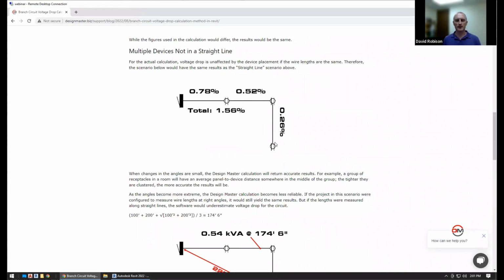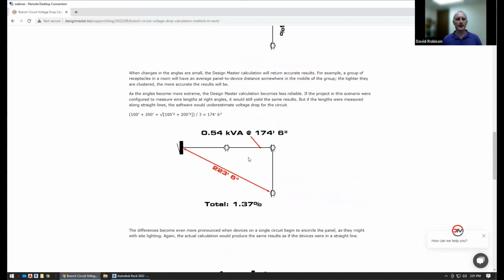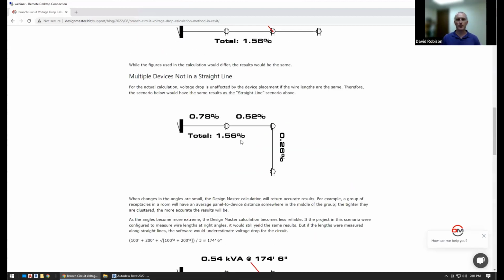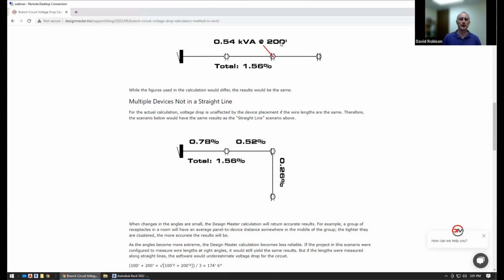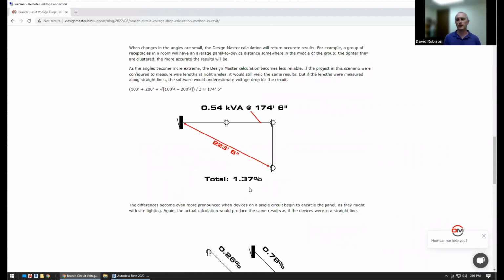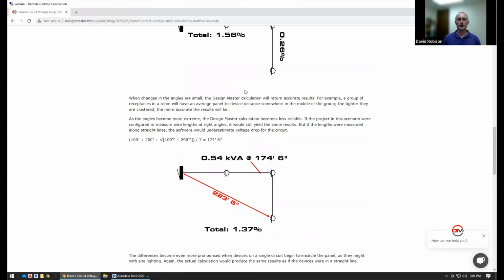So rather than having a straight line, we actually make a curve. We make a turn. So here, if you calculate it by hand, you get obviously the same voltage drop because while we've changed this location, the distances haven't changed at all. So we get the same calculated value. In Design Master, we have 100 feet and 200 feet to these two. If we're doing a straight line calculation, it's going to do a calculation straight to this one, which ends up being about 223 feet. And the average distance is 175 feet as opposed to 200 feet. So it sees it as a shorter distance, and so we are going to end up with a smaller voltage drop. In this case, we're undercounting the voltage drop, so it's a little bit lower than it otherwise would be.